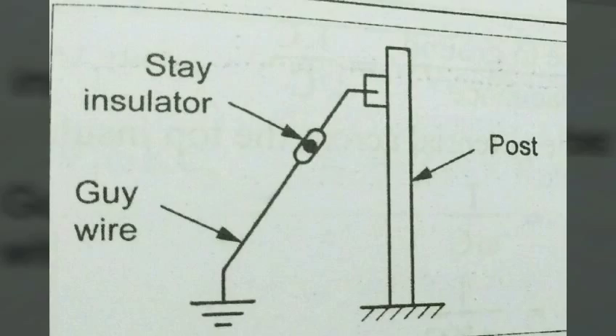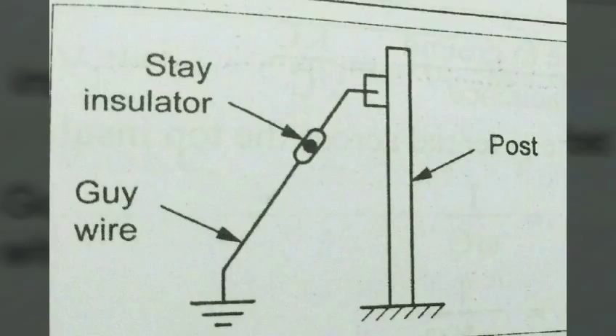Next, stay insulators or egg insulators. The stay wire or guy wire is used to support the dead end poles and keep the poles in position. The insulator used in the guy wire is called a stay insulator. The shape of this insulator is egg-shaped, so it is also called an egg insulator. It is also used to avoid leakage current flowing through the lower part of the guy wire.